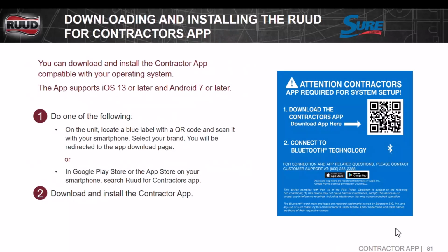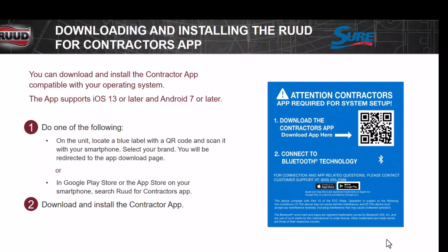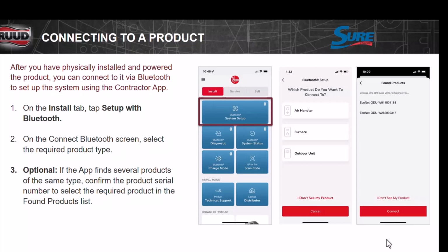We're a little different than most. Whenever you get to the unit, you're going to see this tag on like the furnace or air handler. So this is the contractor app. We have already run into this, but you have to have an iOS 13 or later device or an Android 7 or later device. So your iOS software has to be at least 13. So getting into the unit, connecting to the product, you're going to go in, open your Bluetooth app, and click the setup button. When you do, you'll see the pieces come up: air handler, furnace, condenser. You'll see the model and serial number of the pieces come up. That's how you determine if you have more than one piece in the house. Let's say you have two systems and you're setting both of them up. You go by the serial number so you know which one you're changing the settings on.